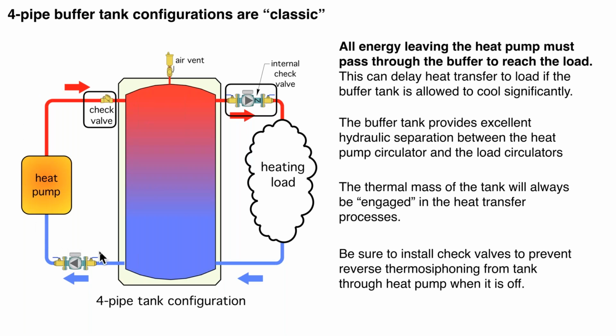All right. This was a huge problem with solar thermal collectors going back 40 years ago. I don't think anybody really realized how much of a factor that was going to be. And it becomes a factor really in any system where you have a thermal storage tank and a piping loop that is not blocked. And remember, a circulator without a check valve in it does not block flow. Flow can go backwards through a circulator when it's off.